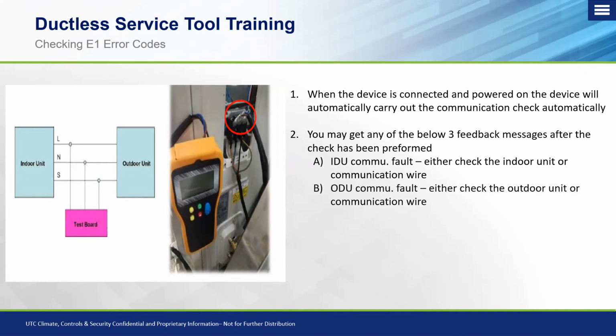The second code would be your outdoor communication fault. So you either need to check something within the outdoor unit or a communication wire. This does not automatically mean to replace the board. You need to do your due diligence and make sure there are no loose signal wire connections on there, or something on the board that might be smoking. You see it on the board, confirming that it's not getting power, or it's getting power but it's not powering on, which is why you have E1. Now, of course, that would be a board in that scenario, but don't assume that it's just a board. Do your due diligence and troubleshoot.